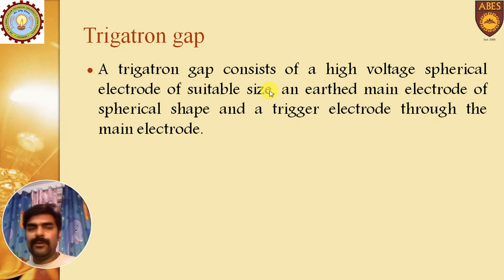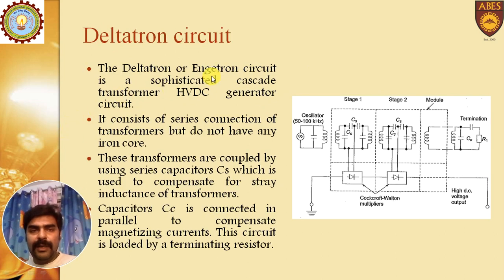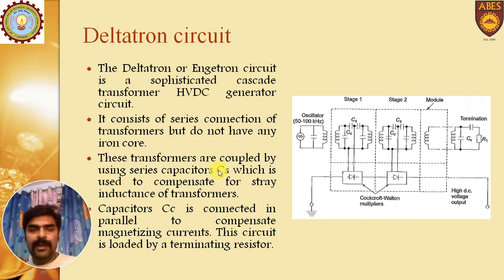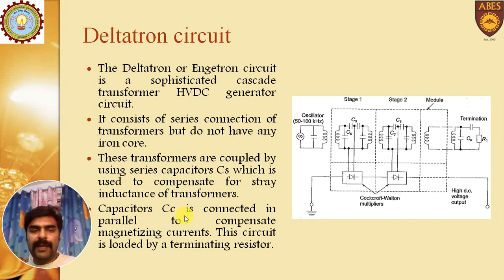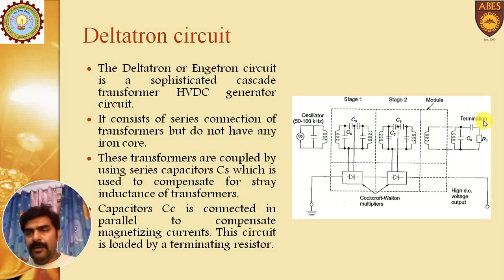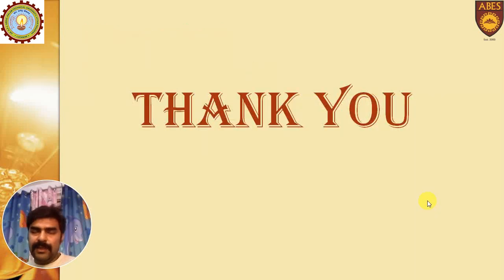The next topic is the Deltatron or Engetron circuit, which is a cascaded transformer HVDC circuit. It consists of a series connection of transformers without any iron core — stage one, stage two, and further modules. These transformers are coupled by series capacitors Cs, and a capacitor Cc is connected in parallel to compensate magnetizing current. The circuit is loaded by a terminating resistor and is used for the generation of high voltage.